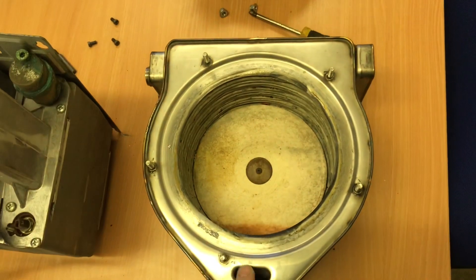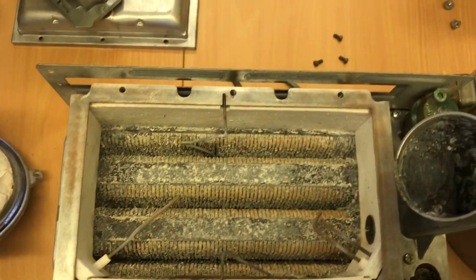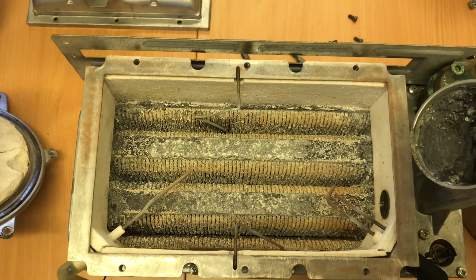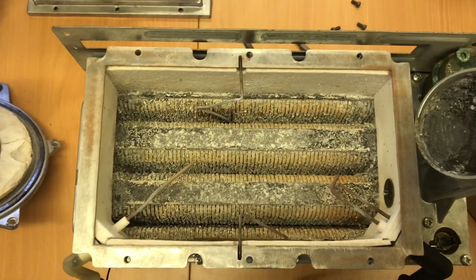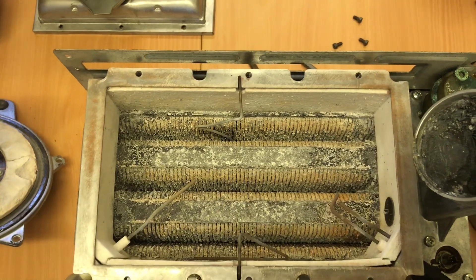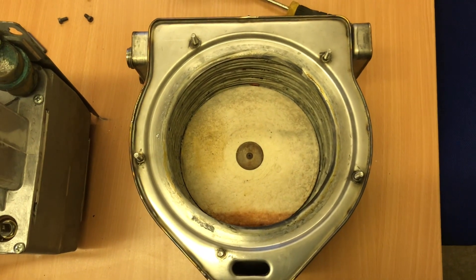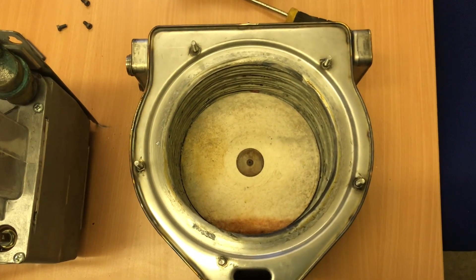Products of combustion go down, out through the back, up through the top, and out through the fan at the top — making it a more robust heat exchanger. The only downside is you can extract more heat from aluminium than stainless steel, so many manufacturers are going back to aluminium, using cast aluminium rather than silica-based aluminium. However, the stainless steel, while slightly less efficient, is far more robust than aluminium.